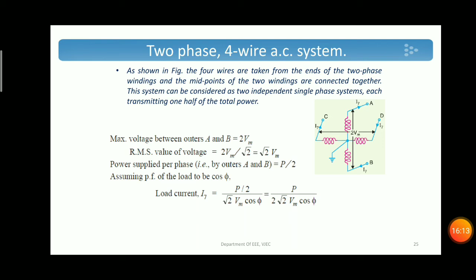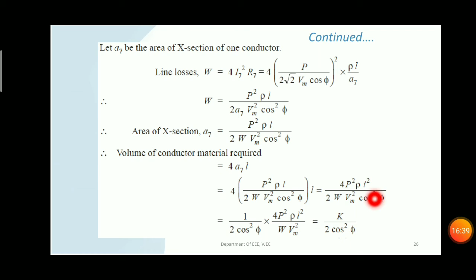Power supplied is P by 2 per phase, since there are two single phases. So load current is P by 2 by root 2 Vm cos phi. Then the line loss is, as there are 4 wires, 4 into I7 square R7. Substitute for I7, then we can find the value of A7. The volume of conductor material required, on substituting for A7, we will get as K by 2 into cos square phi.